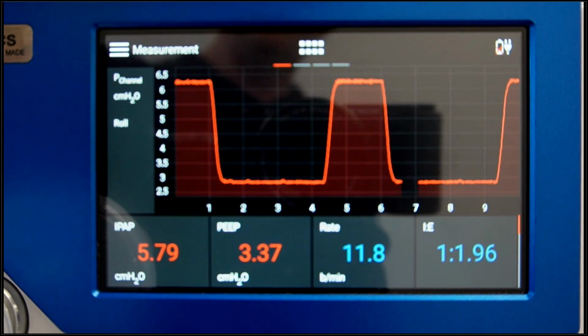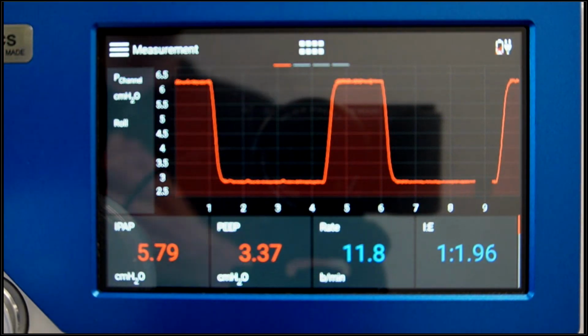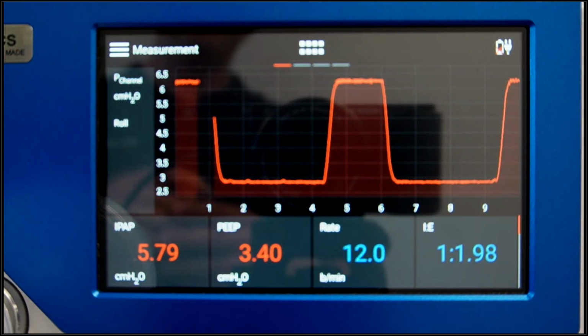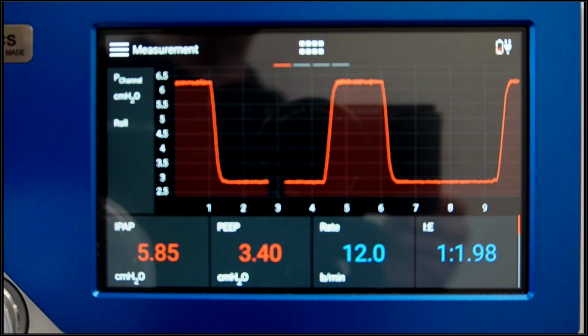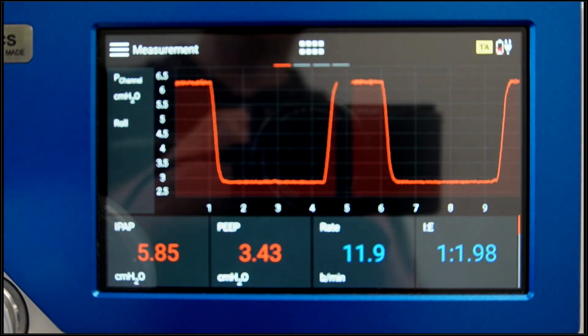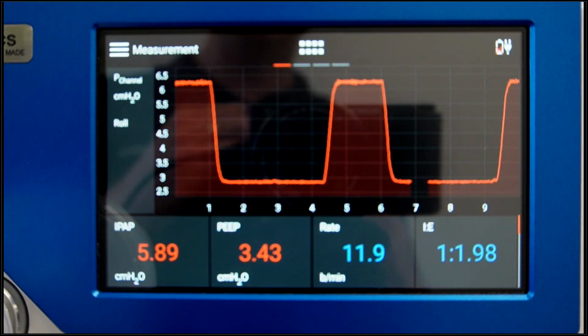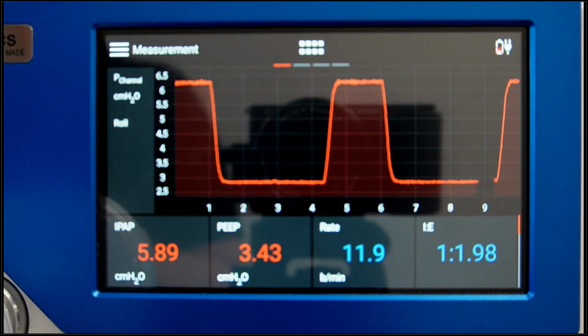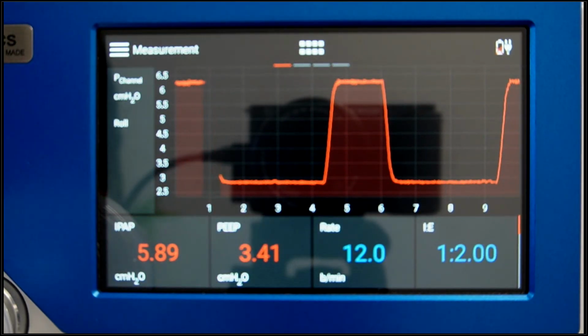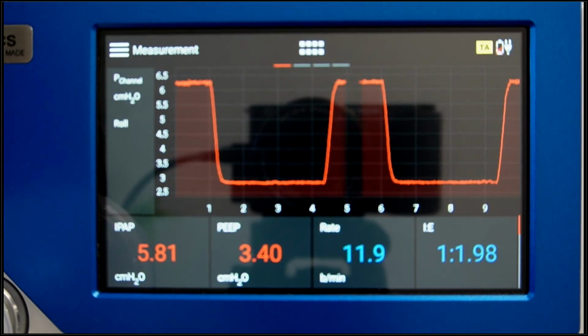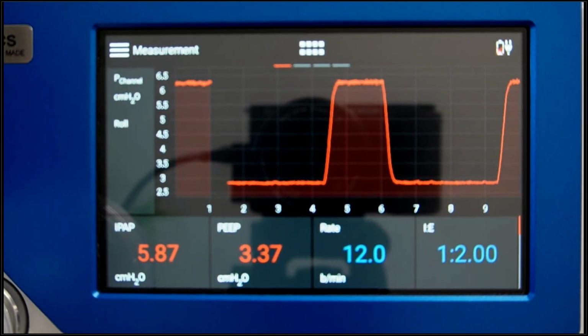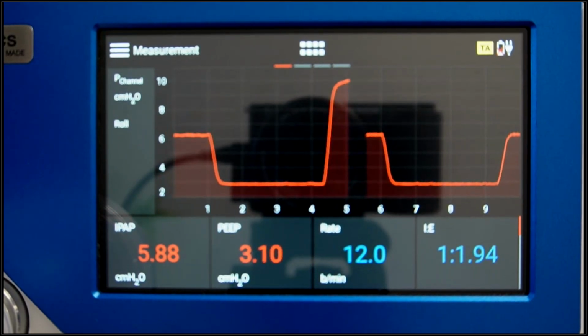What is the case now? So now I can measure my breath-based parameters. So let's assume that this was the first setting I had to check on this ventilator, IPAP of 6 and EPAP of 3. And let's assume the next setting set is IPAP of 10 and EPAP of 5. So I'm just going to change that on my ventilator here a little quick. So my next settings are IPAP of 10 and EPAP of 5.